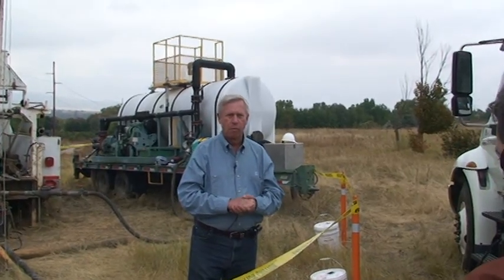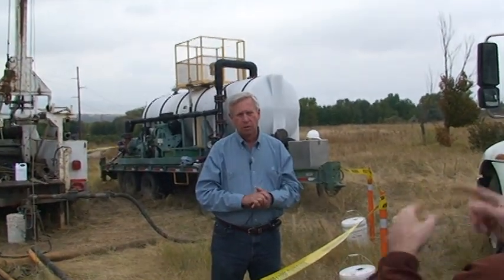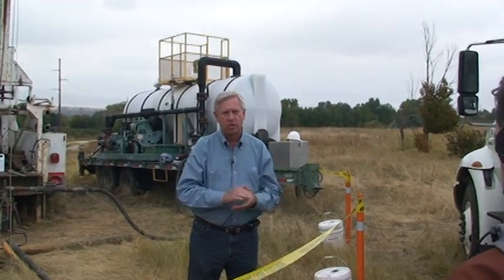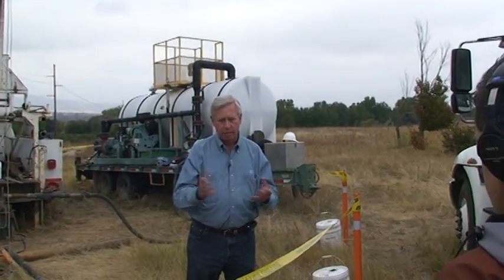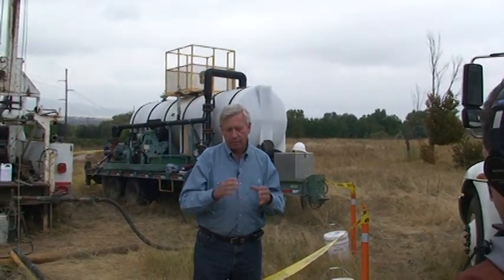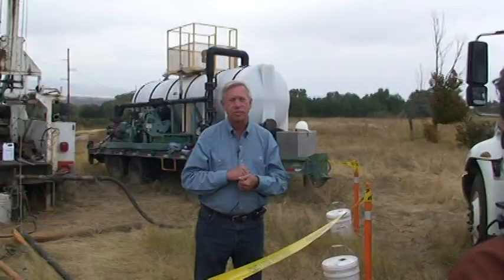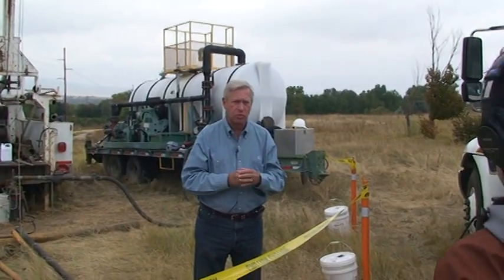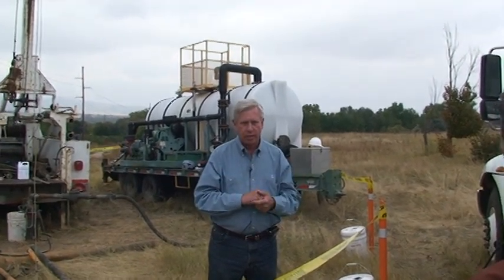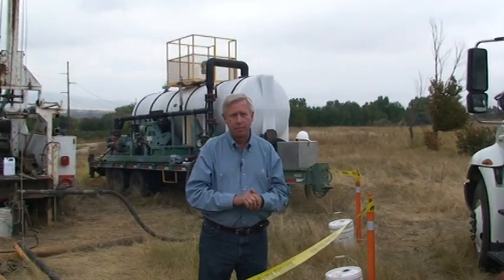Wow. So you already kind of answered this, but I'm gonna retouch on it. What is the process you're doing today, and how long will that take? Today is pumping out the super chlorinated solution so that the well is back to the natural water conditions. That'll take the rest of the day, I imagine, a few hours to the rest of the day from now. And then it'll sit and they'll do a video when that's scheduled. I don't know when the video is scheduled for, today or tomorrow, but it'll be soon. Make sure the well's clean again, and then we'll get the test pump out here, and the contractor Lane will put the test pump in and do a 24-hour pump test on it so we can determine the parameters for the final design of a new pump and motor.